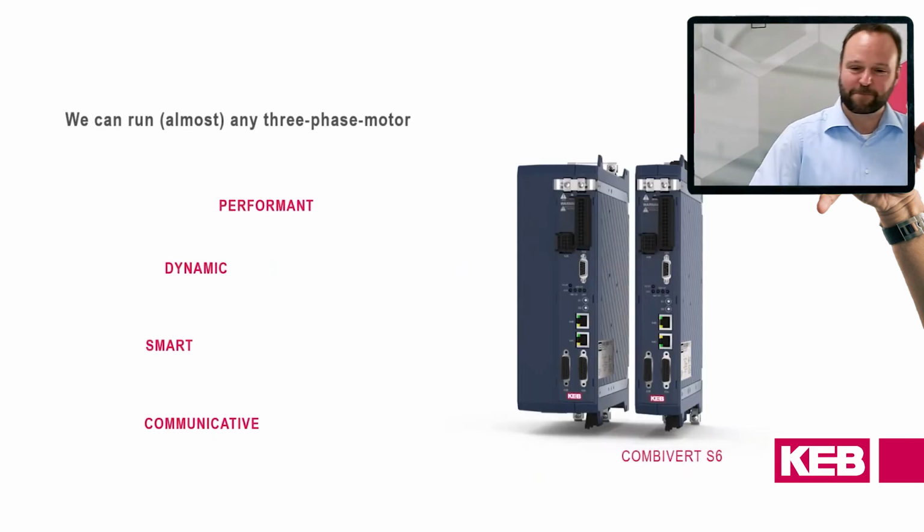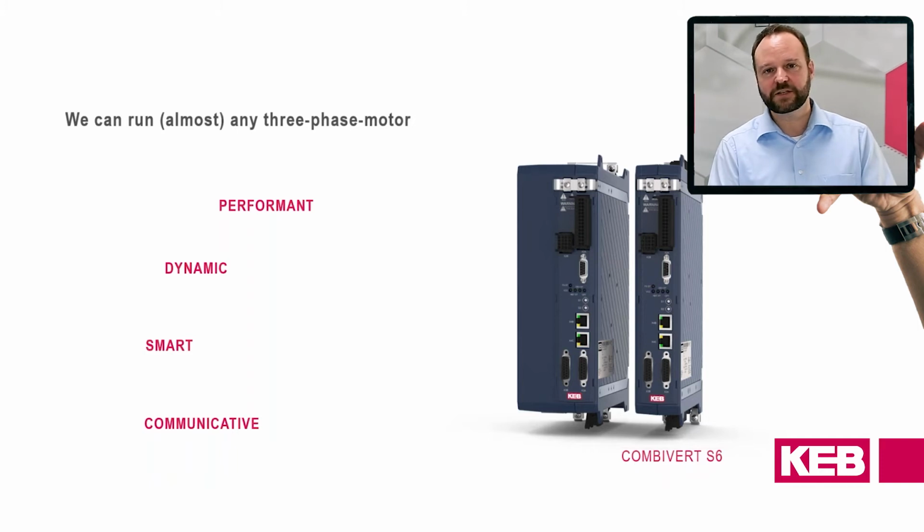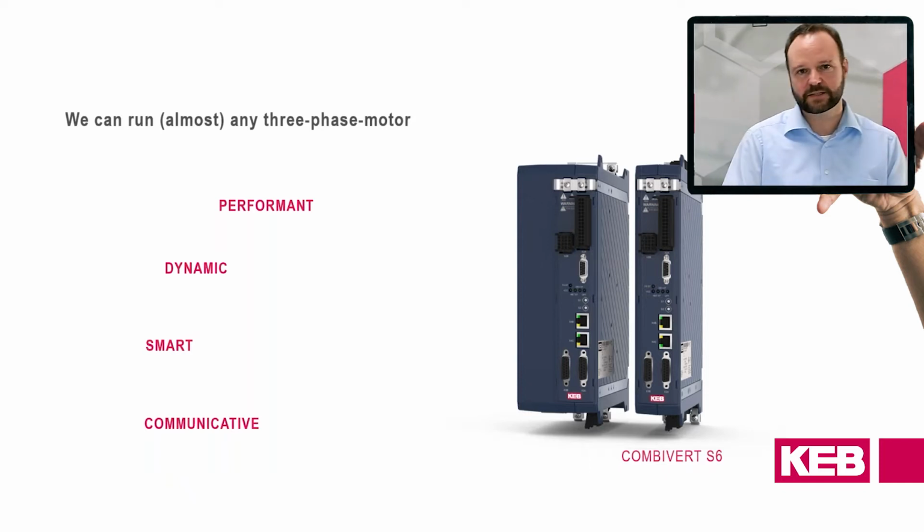So, talking about scalability, we also have to talk about motors, encoders, and field bus systems. We can handle with our drive different kinds of motors, like asynchronous machines, synchronous machines with surface-mounted magnets, with internal permanent magnets, synchronous reluctance machines. Then, of course, linear motors, high-speed motors like spindles, up in the kilohertz range, and also high-pole, low-speed, high-torque motors.